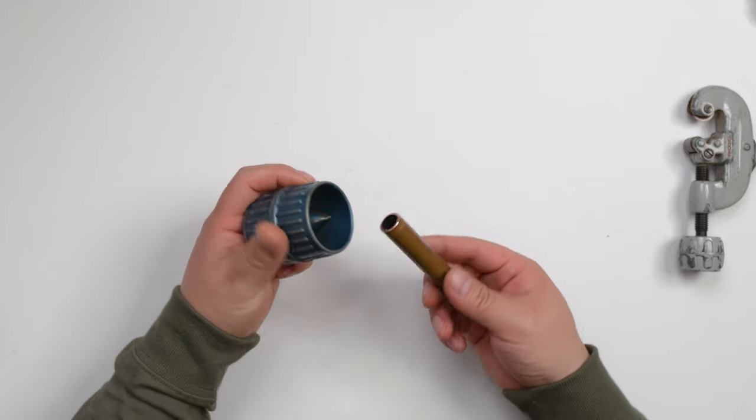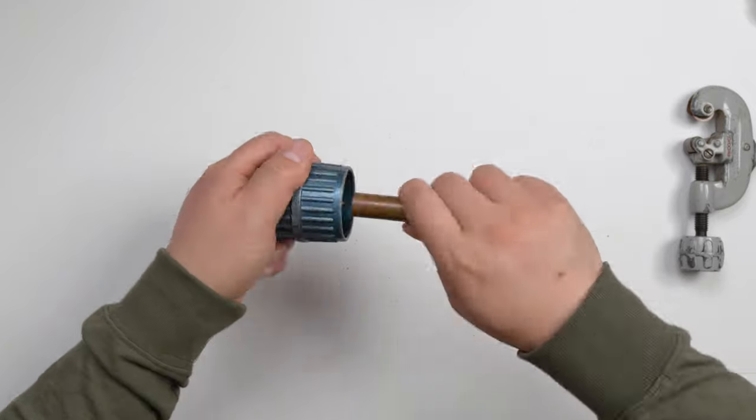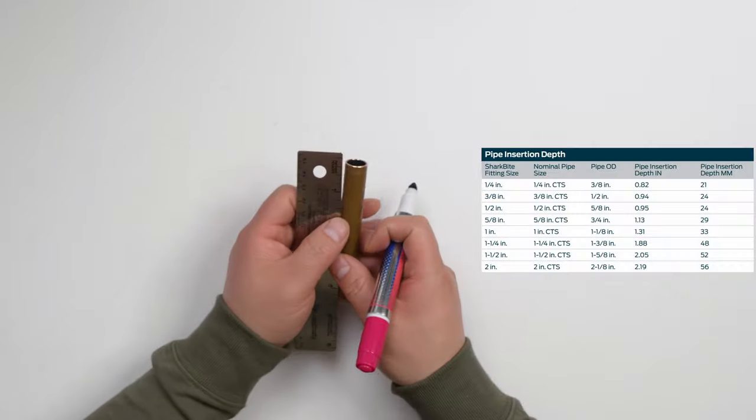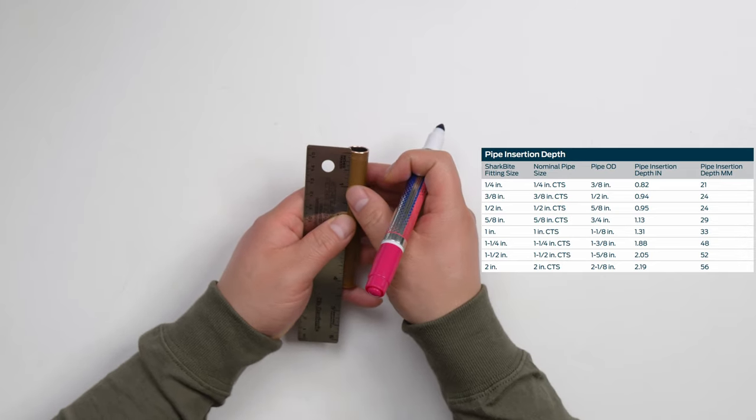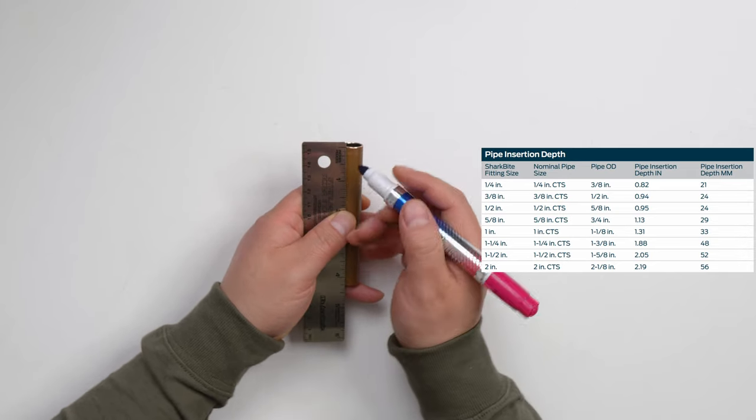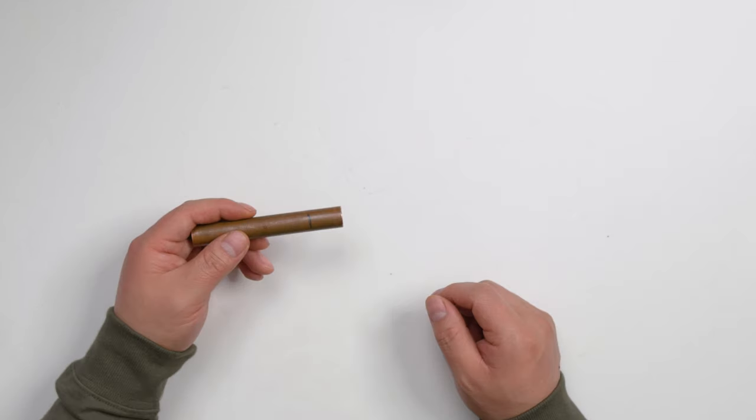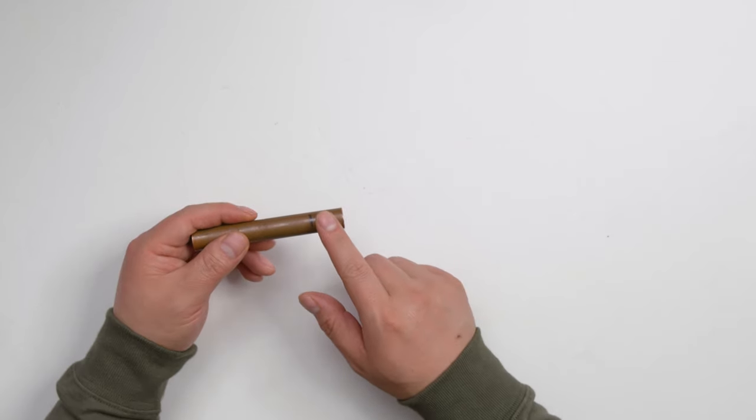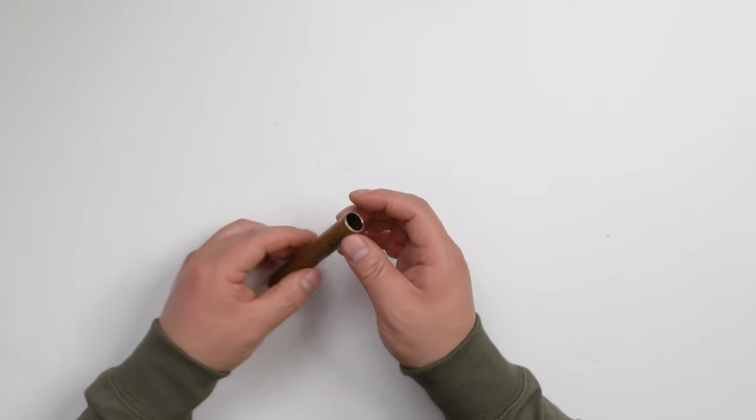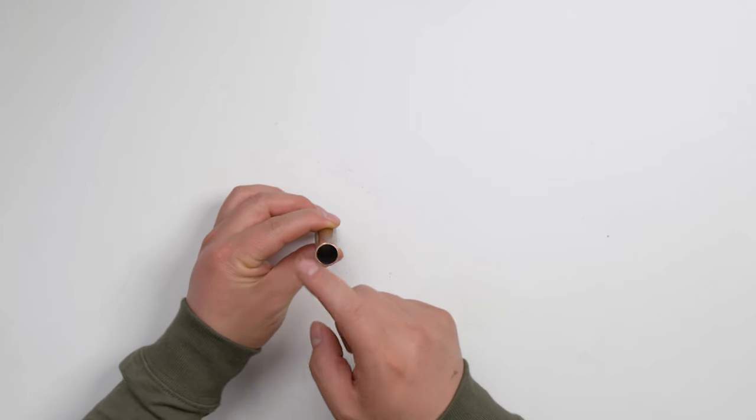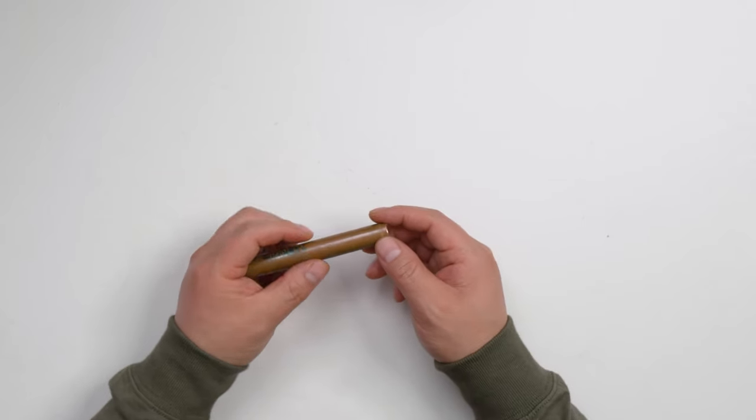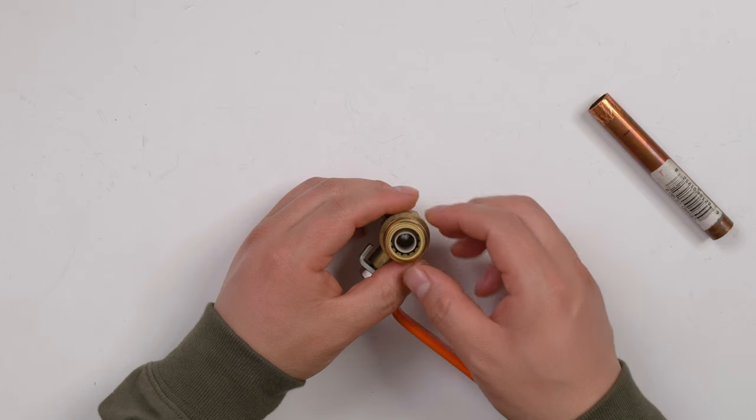Let's use this side to clean the inside, then mark the copper at 0.95 inches. You don't need to use sandpaper to sand the surface, but you're going to make sure that the copper tube is round and there's no dirt or damage. Let's check the push connection.